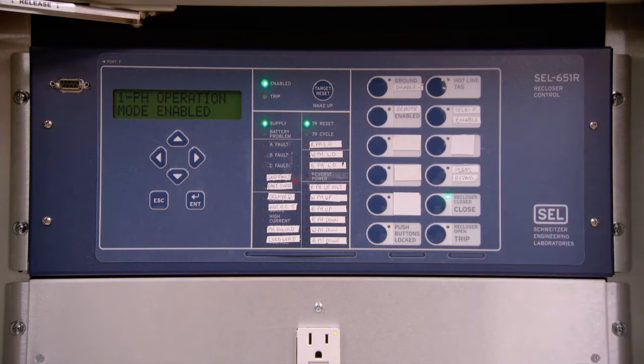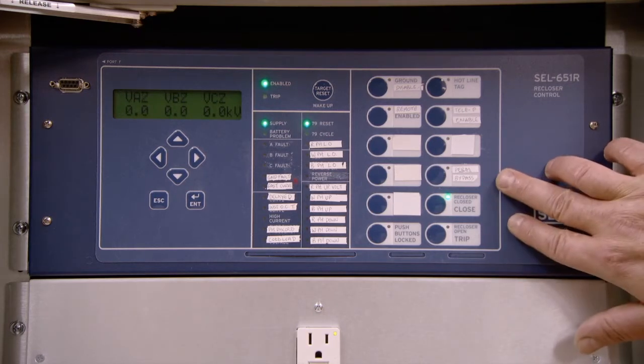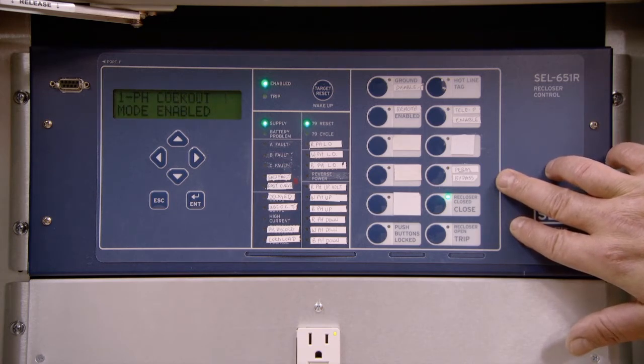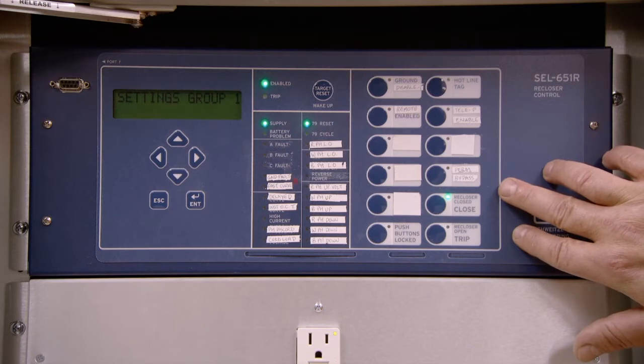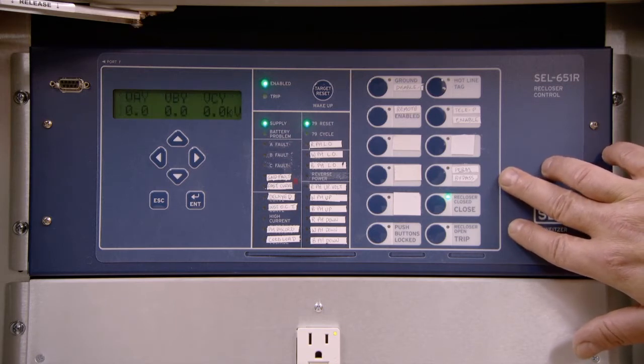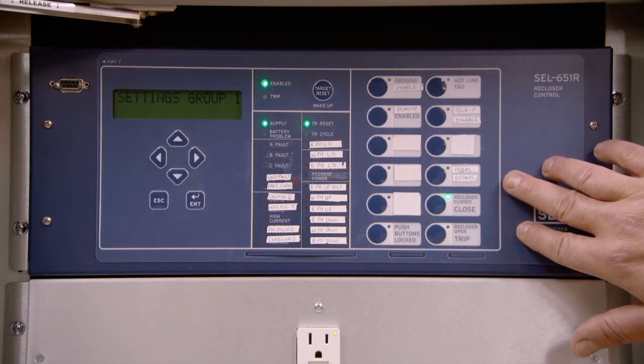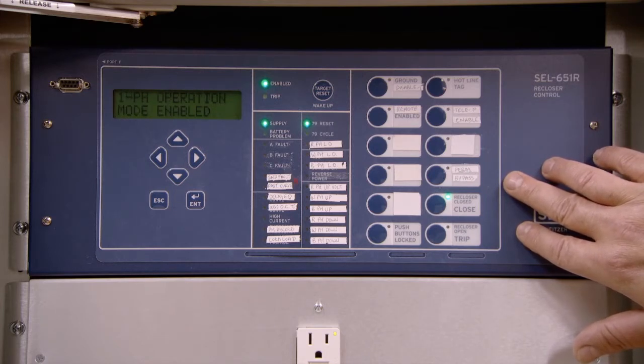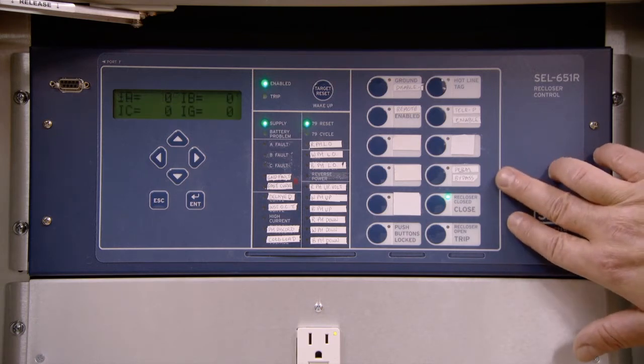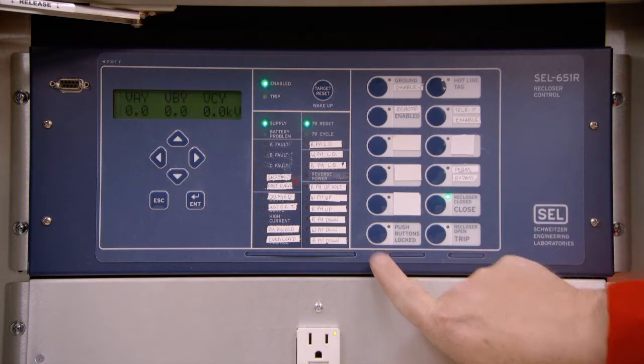Permissive bypass. If this controller was set up for a generator communication connection, you would also set a permissive bypass. If then there was a radio communication failure, the permissive bypass would take the radio communication switching function out of the sequence, and the recloser would then go through its full normal functionality. From the generators going back online past this recloser, the controller will be looking for a permissive signal from them. That signal is called a DGO signal. If radio communications go down, that control link will have to be disabled. Once again, it's a two-fingered operation to enable or disable this feature.